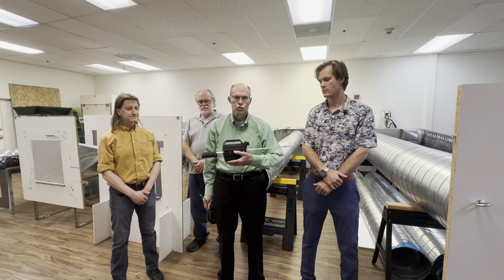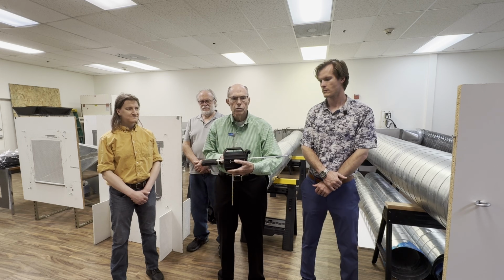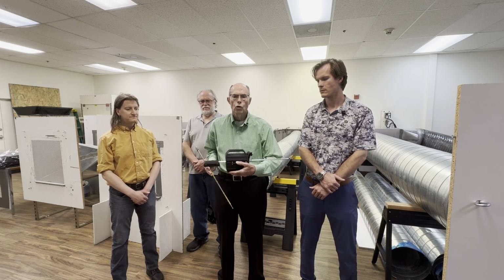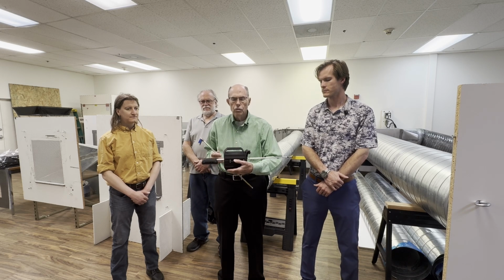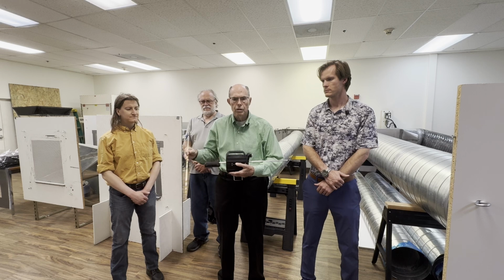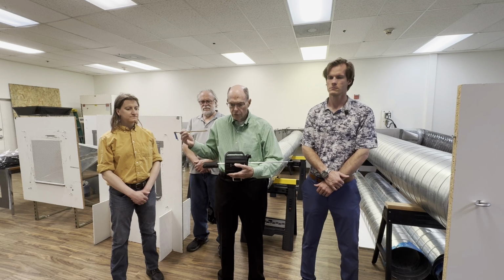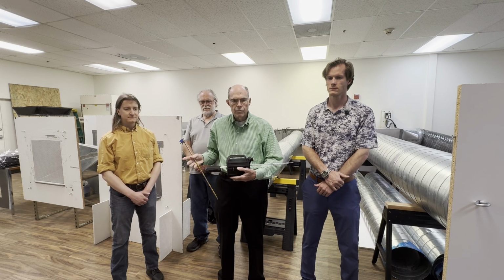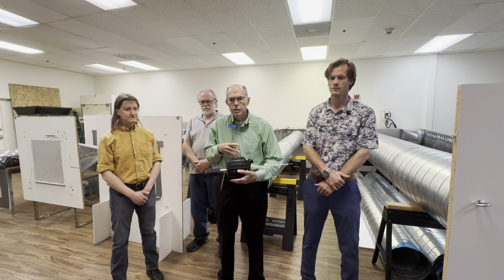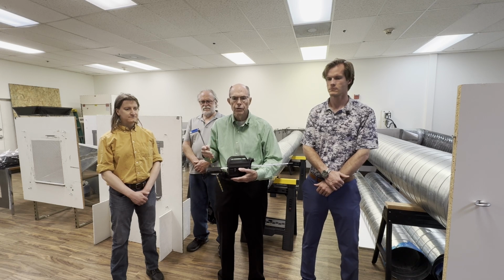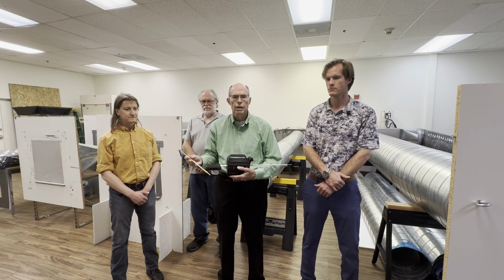I sure wish I had this machine then, because every result will be perfectly consistent with the next. Not only can this machine test a duct one time to get an individual result, but you can leave it in place, and if a technician is working in a particular area over the next hours or days, he can program the tablet computer to get a traverse result every 5 minutes or every hour. So as he's balancing the building, he has real-time awareness of how much air is flowing past that point in the duct.